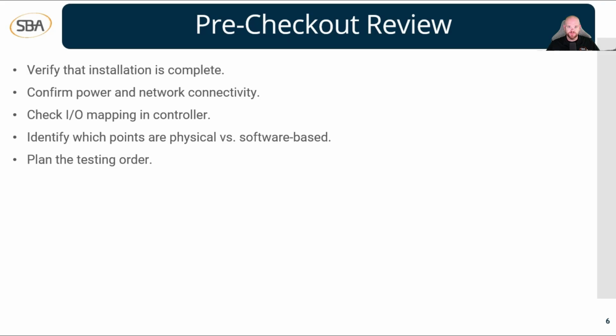So we're going to get in our software. We're going to take that I/O schedule that we were talking about a little bit ago, and we're going to check and make sure that our inputs and outputs are mapped to the controller just like they're supposed to be per the schedule, okay? So that's what this is saying. Check the I/O mapping in the controller, use that schedule, double check your mapping, make sure everything's right.